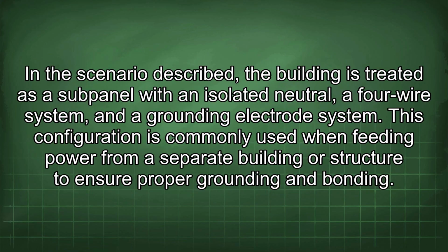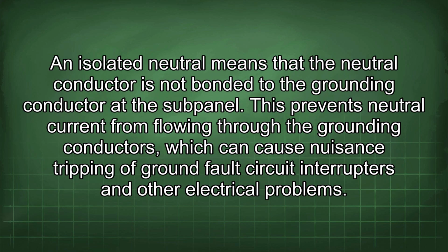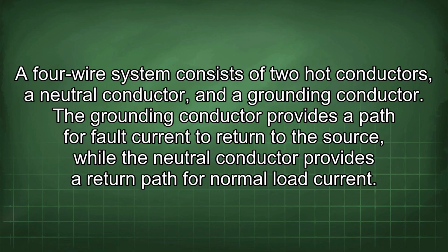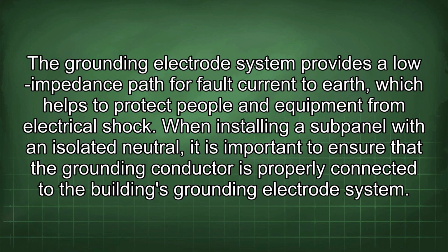In the scenario described, the building is treated as a sub-panel with an isolated neutral, a 4-wire system, and a grounding electrode system. This configuration is commonly used when feeding power from a separate building or structure to ensure proper grounding and bonding. An isolated neutral means that the neutral conductor is not bonded to the grounding conductor at the sub-panel. This prevents neutral current from flowing through the grounding conductors, which can cause nuisance tripping of ground fault circuit interrupters and other electrical problems. A 4-wire system consists of 2 hot conductors, a neutral conductor, and a grounding conductor. The grounding conductor provides a path for fault current to return to the source, while the neutral conductor provides a return path for normal load current. The grounding electrode system provides a low impedance path for fault current to earth, which helps to protect people and equipment from electrical shock.